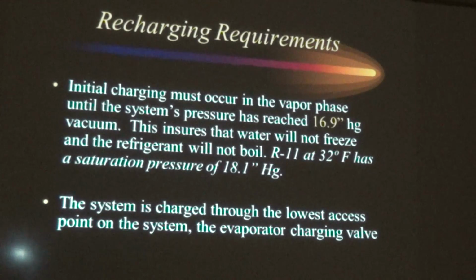Initial charging, after you've made your repairs and you're ready to recharge the system, must occur in a vapor phase until the system pressure has reached 16.9 inches of mercury vacuum. This ensures that water will not freeze and the refrigerant will not boil. R11 at 32 degrees Fahrenheit has a saturation pressure of 18.1 inches of mercury. So if you're using R11 refrigerant, you have to get the pressure up to, it sounds weird saying up to when we're talking about a vacuum, but up to 16.9 inches of mercury vacuum.